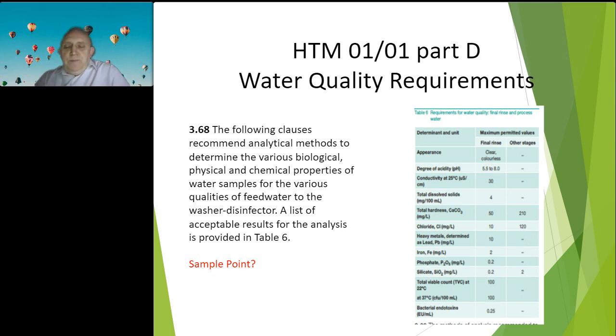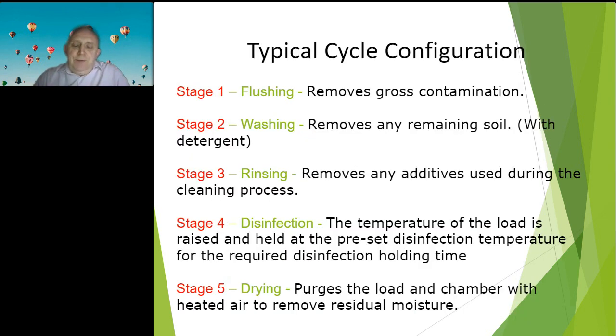You know, a washer disinfector is connected to a source supply by a flexible hose. Flexible hoses are known to develop biofilms, so we need to make sure we sample at point of use. I think that's very important when you're collecting water samples. So if we look at the typical washer disinfector cycle configuration, generally 5 stages.